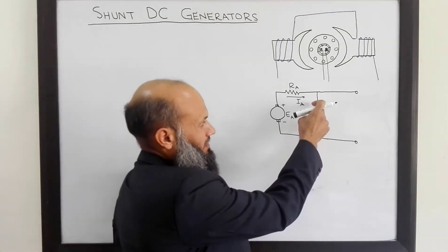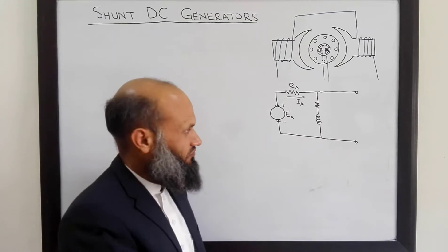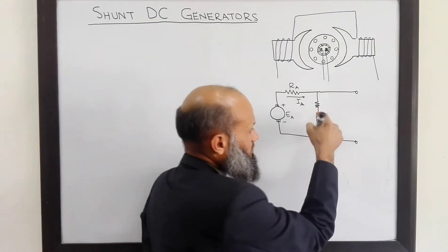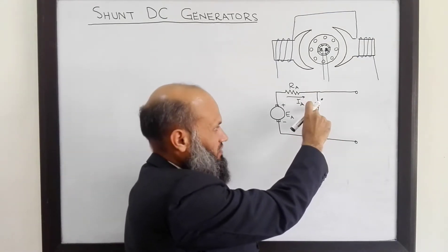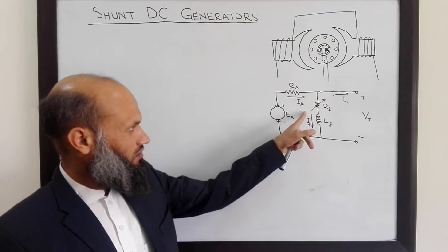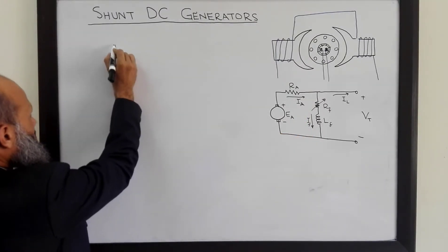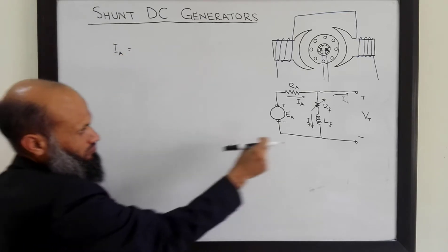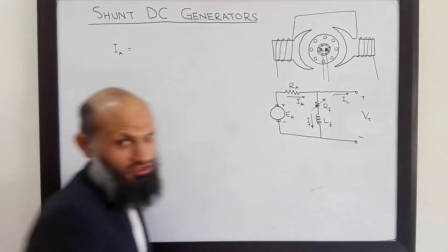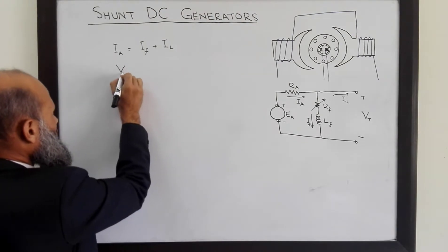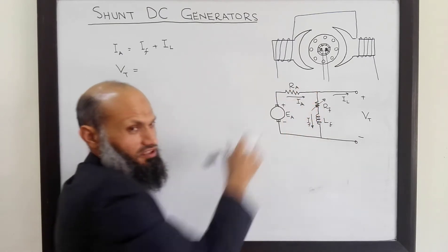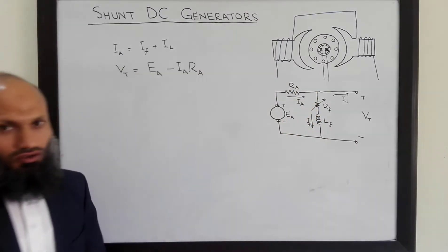Sometimes an additional variable resistor is inserted in series with the field windings, which gives us control on the terminal voltage. The resistance of the field winding combined with this variable resistor gives us the total field resistance. In shunt DC generators, the armature current equals the sum of the current which flows in the field winding and the current which flows in the load.